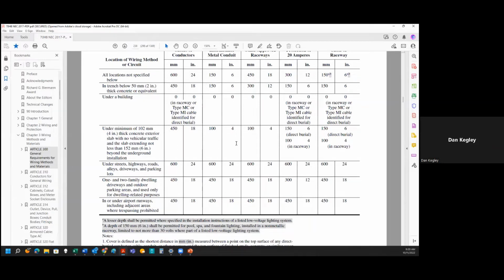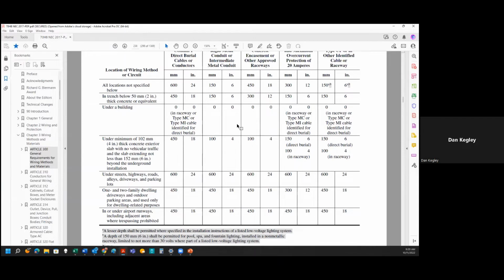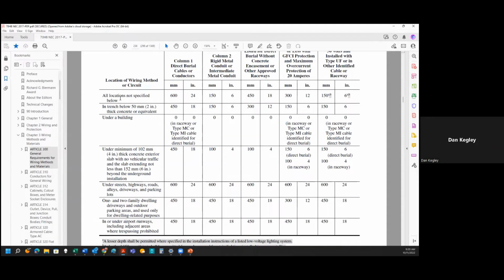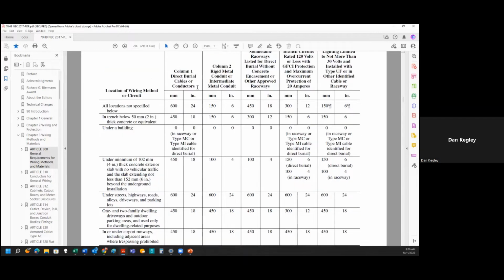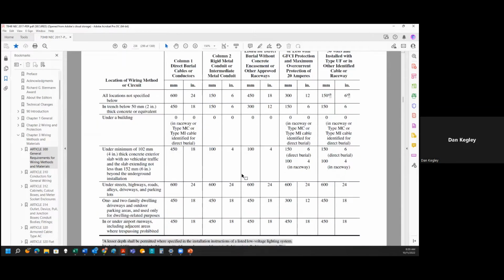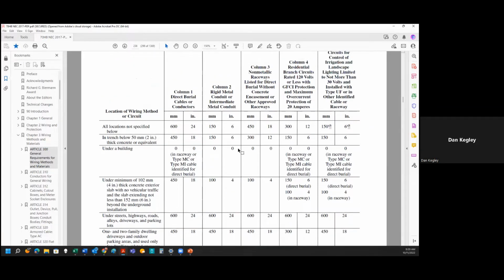There are some exceptions here. You can see other locations not specified below. You can get 6 inches of depth in trenches below with 2 inches of concrete, so 6 inches versus 18 inches. So there are some exceptions here, but you've got to look at the chart. It's not quite the same as the 18 and 24 you would find with just the cable itself. Yeah, there's a lot of variability there. So just put it at 24 inches.